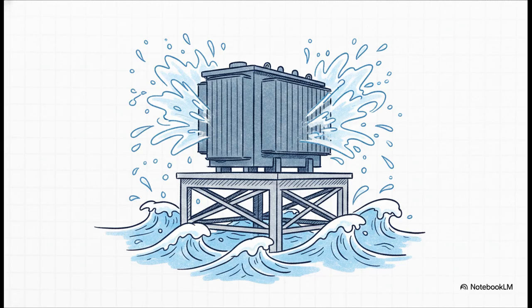Think about it. Because the platform is unmanned, the fire risk to personnel is practically zero. But more importantly, that relentless salt spray means you absolutely need a fully sealed system to prevent rapid corrosion. If you stuck a dry-type resin transformer out there, that humid, salty marine air would eat it alive and crack it way faster than you'd expect. Plus, the oil's efficient cooling gives you a much more compact footprint, and offshore space is premium real estate.